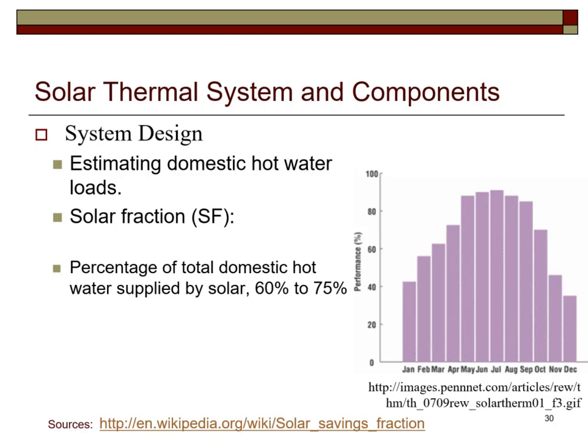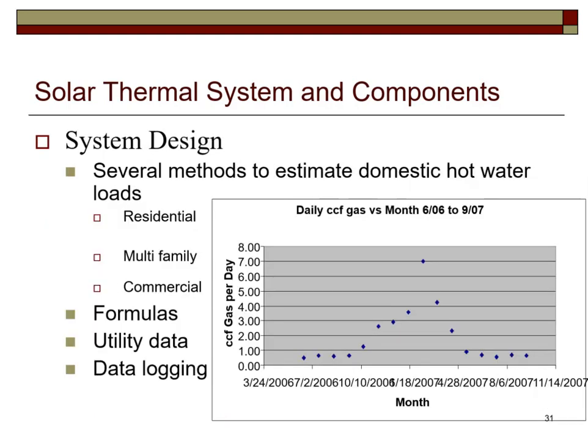When designing a system to meet hot water needs, the system is usually not designed to meet 100% of the hot water needs. Doing so would result in the system overheating in the summertime. The systems are usually designed to meet 60 to 75% of the hot water needs. This percentage of hot water which is met by the solar thermal system is referred to as the solar fraction. There are several methods to determine hot water requirements. The first one, which was previously mentioned, is referred to as the formula method. There is also the method of using utility data and also the method of data logging.